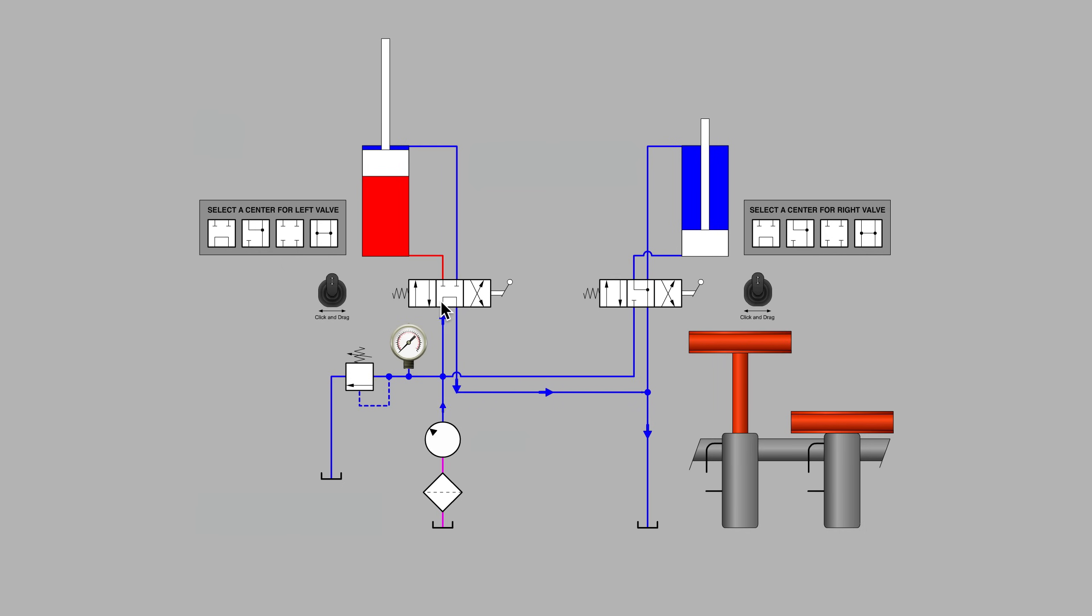And our pump is unloaded back to tank whenever the valves are in their neutral position, center position. But what about the valve on the right and the cylinder on the right? Are we able to raise that cylinder? No, we cannot because once again, we have that leakage path through the valve on the left hand side.